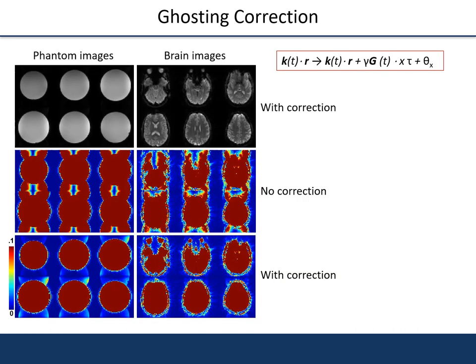Similar to EPI, the alternating nature of the CEPI echo train leads to ghosting artifacts due to gradient imperfections. A linear model was used to correct the K-space prior to reconstruction. This way, ghosting artifacts could be reduced to a few percent of image intensity. Brain and phantom images before and after the correction are shown on this slide.